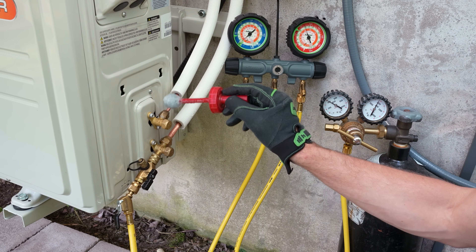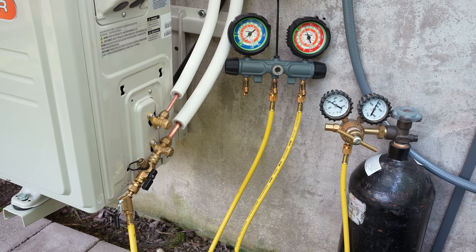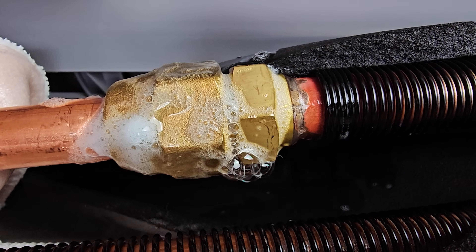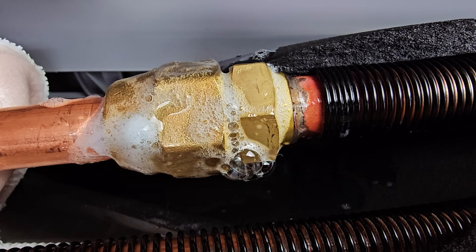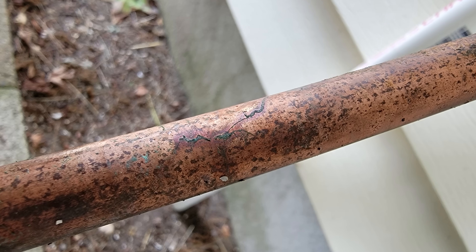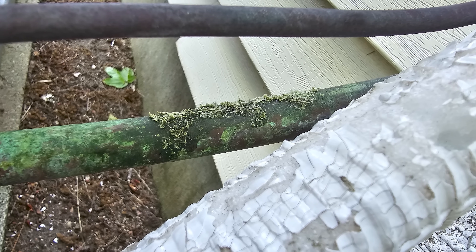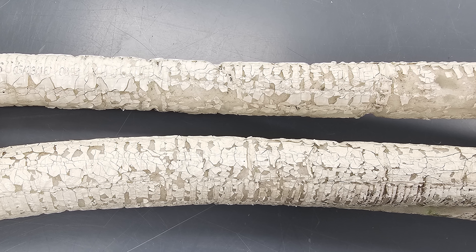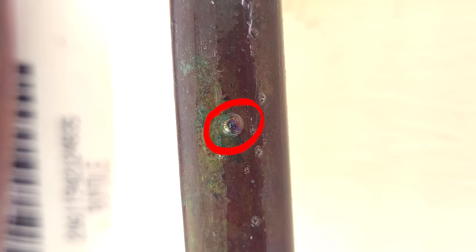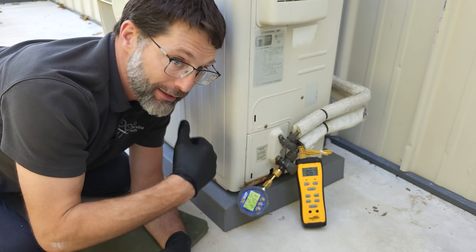A leaky flare joint could have happened during the initial install — the technician didn't completely pressure test it or leak check it with non-corrosive bubble leak detectors. You could also have a leaking outdoor coil or indoor coil, or corrosion on the line sets leading to pinhole leaks due to white insulation breaking down and causing a chemical reaction that eats away at the copper tubing from the outdoor unit to the indoor unit, causing the refrigerant to leak out.